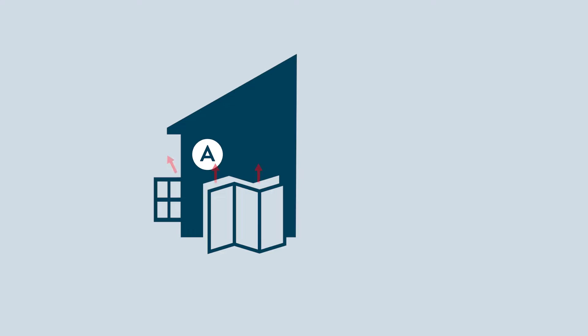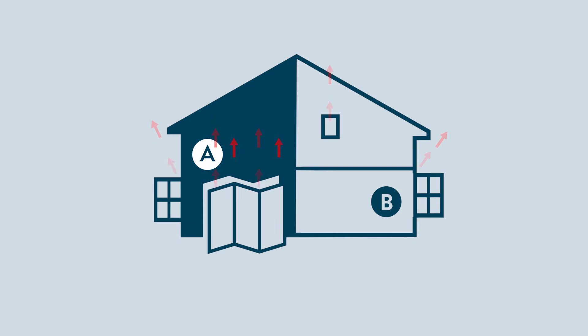For example, you might have two rooms next to each other in your house that are exactly the same size but have very different requirements. One room might have three external walls and bifold doors, and the room next to it, whilst exactly the same size, may only have a small window. These rooms are going to have very different requirements in terms of heat output from the underfloor heating, which is why this approach of heat loss calculations must be bespoke to each room.